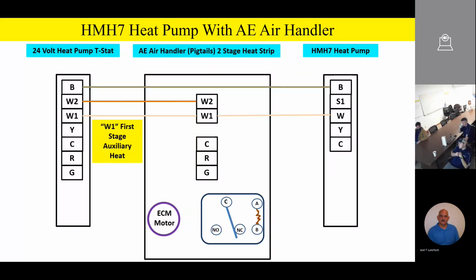This is very typical. Now, one thing I need to make everyone aware of as well, based on your heat pump thermostat, we show a W1 and W2 on the heat pump thermostat, but please remember, based on the brand of thermostat that you buy, the W1 and W2 signals might be called AUX, A-U-X. They might be called W1 and W2. They may be called EM/W, for emergency heat / W for auxiliary heat. So just be aware that whatever thermostat you're looking at, what you're looking for is your W1 signal will be your first stage of auxiliary heat. Your W2 will be your second stage of auxiliary heat, but on some thermostats, they may be labeled a little bit differently than W1 and W2. But just remember, it's your auxiliary heat. It might be AUX, it might be EM, it might be EMW, depending on your thermostat. But just remember, these are your auxiliary heat terminals. Any questions or comments so far?